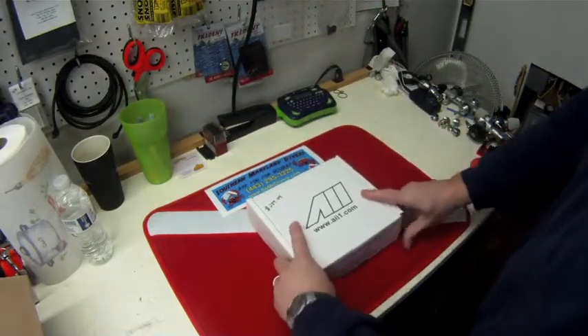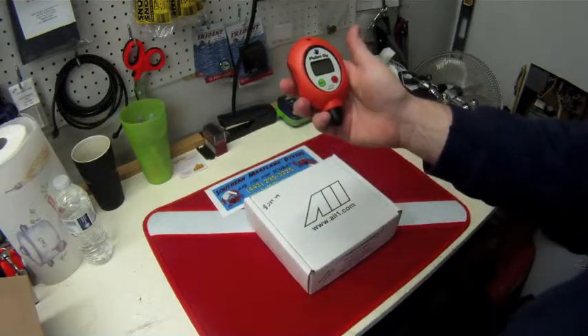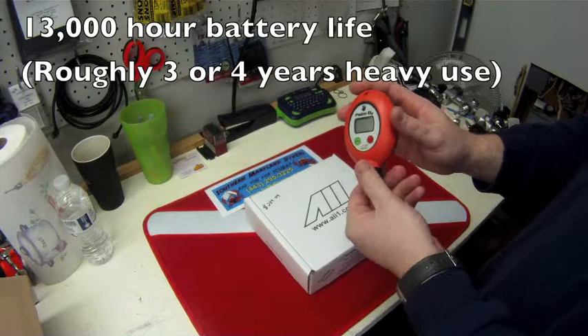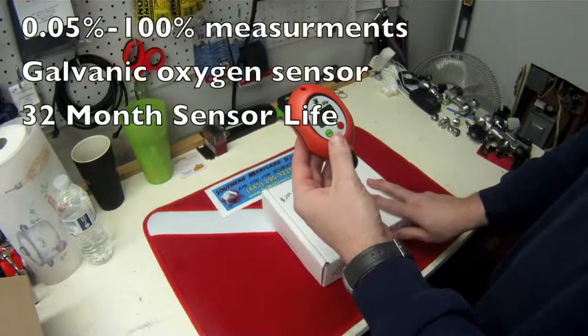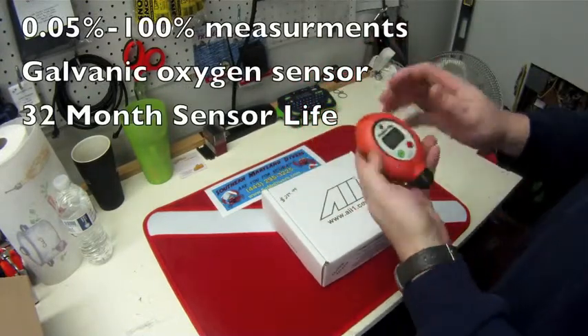I'm actually just going to show you the one that we have here that we use in the shop. So this is the Palm O2 unit itself — comes just like this out of the box. Batteries are installed; they last somewhere in the area of three or four years before you even have to start worrying about the batteries.